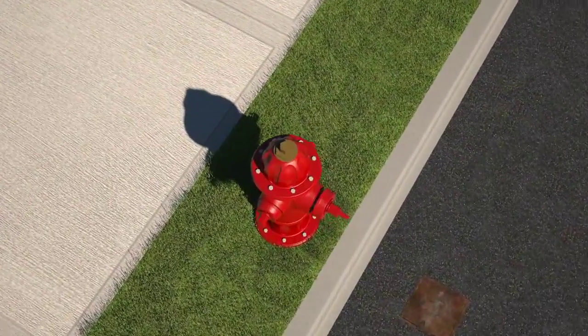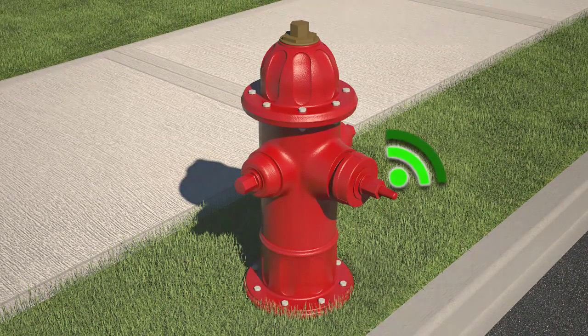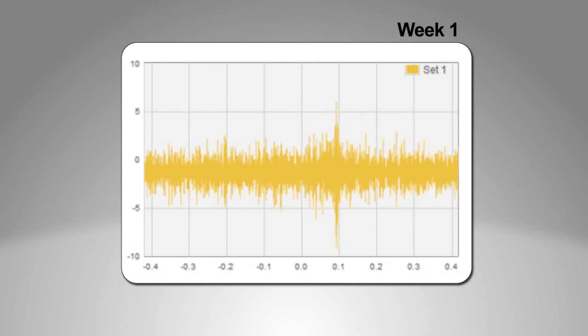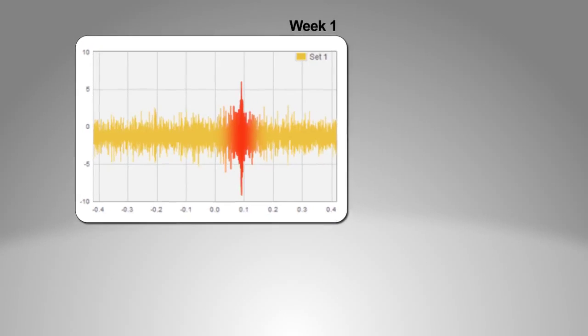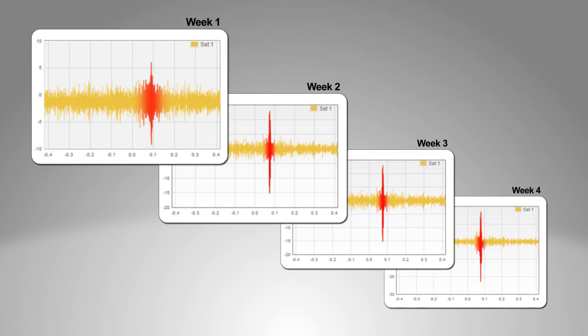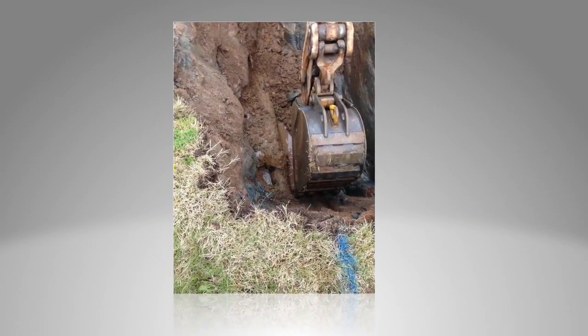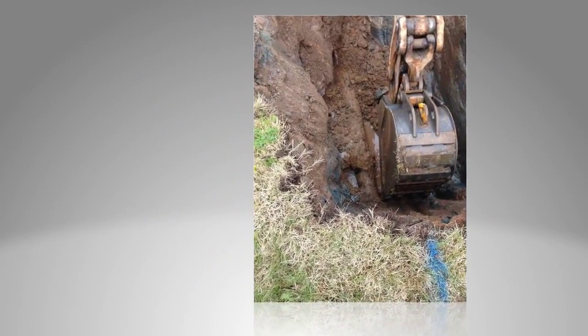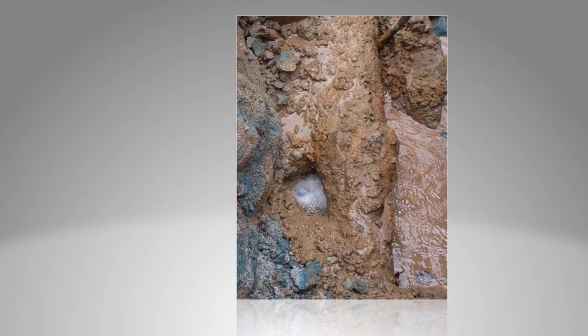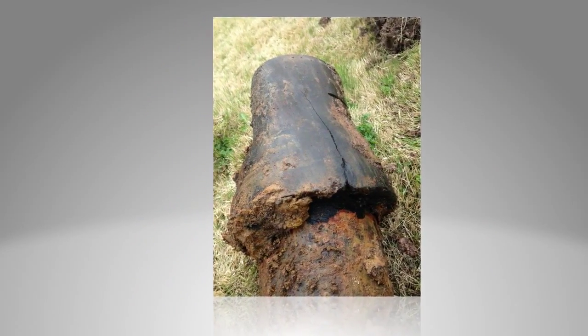Echologics installed EchoShore DX nodes in a community with aging pipeline infrastructure challenges in Pennsylvania. The value of EchoShore DX was quickly proven, as the platform identified and located a leak in the earliest stages of its formation. The leak was closely monitored over a four-week period as it grew in size. Excavation of the identified leak zone confirmed that the aged cast iron pipe had a crack on the bottom of its bell joint. This demonstrates the sensitivity and accurate correlation capabilities of the EchoShore DX platform to catch leaks early and fix them when it is least expensive to do so, before a pipe failure and significant water loss.